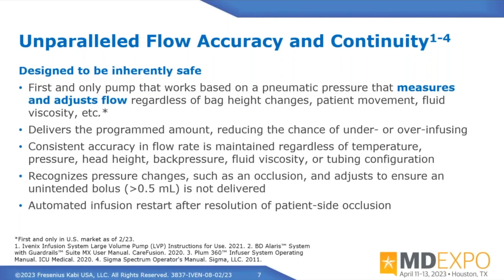And then this is my little garbage in, garbage out conversation. If we think about the roller clamp being missed and the pump thinking that the infusion started, but it didn't actually start, in this situation with control of that secondary infusion, we know that it started and we know that we're accurately delivering it. We're going to alert you that that roller clamp is closed. You'll come back and you'll open it and you'll start the infusion. So anything that's going to impact the accuracy of that infusion is going to alert the nurse or, you know, be compensated for with the technology.